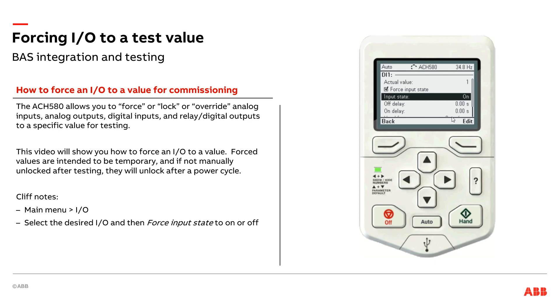I will say that this forced functionality is not meant to be a long-term status. Intentionally, we designed this so when a power cycle occurs, all forced inputs and outputs will clear and go back to their real state. So forced values are intended for troubleshooting, commissioning, and testing scenarios only. I'm going to go ahead and release the force by simply unchecking the box.